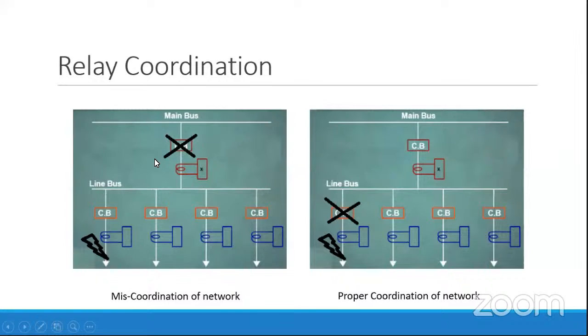If the incomer feeder operates, then a blackout condition occurs in the network, and the power to the healthy feeders will also be interrupted. So the coordination should be done in such a way that only the feeder at which the fault occurs is isolated, not its adjacent feeder or its incomer feeder. In figure A on the left-hand side of your screen, you can see miscoordination of the network. It means a fault occurred in feeder number 1, but the circuit breaker associated with the incomer feeder operated first.